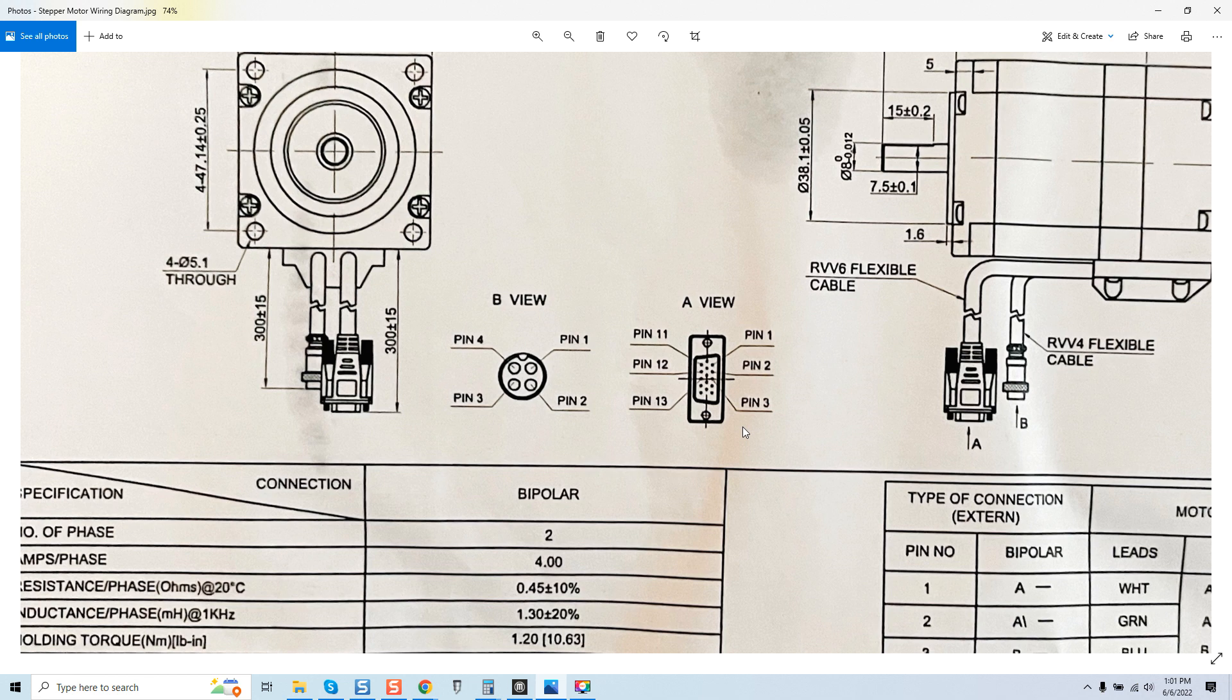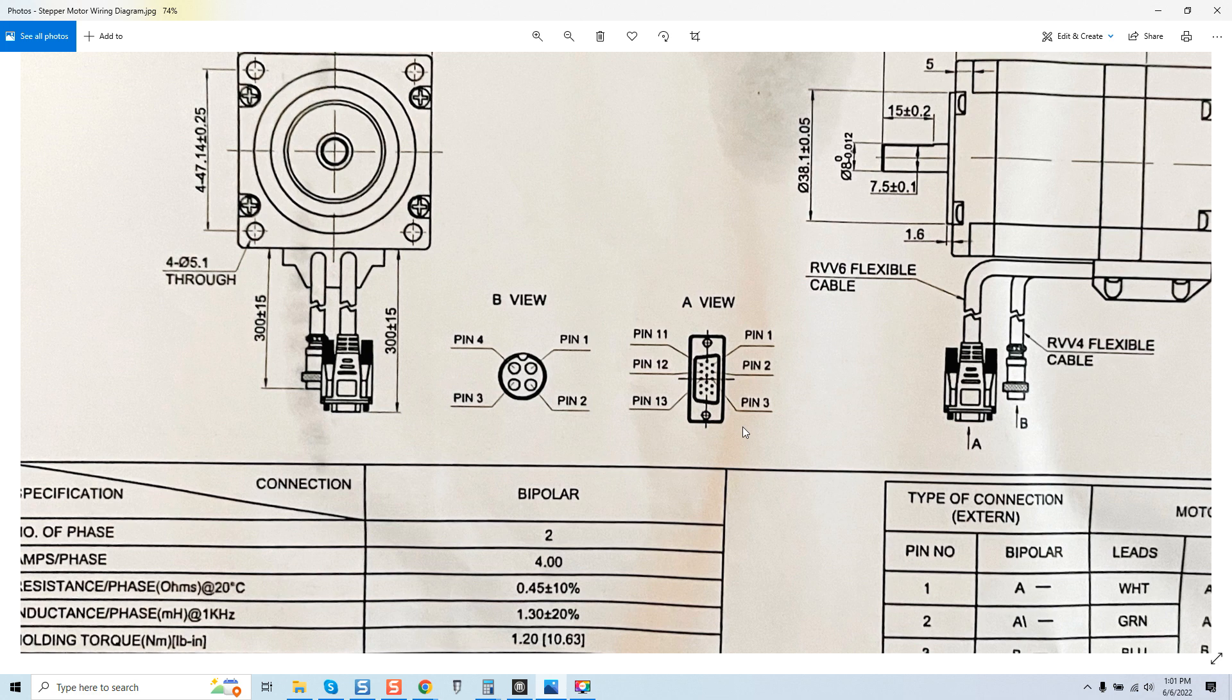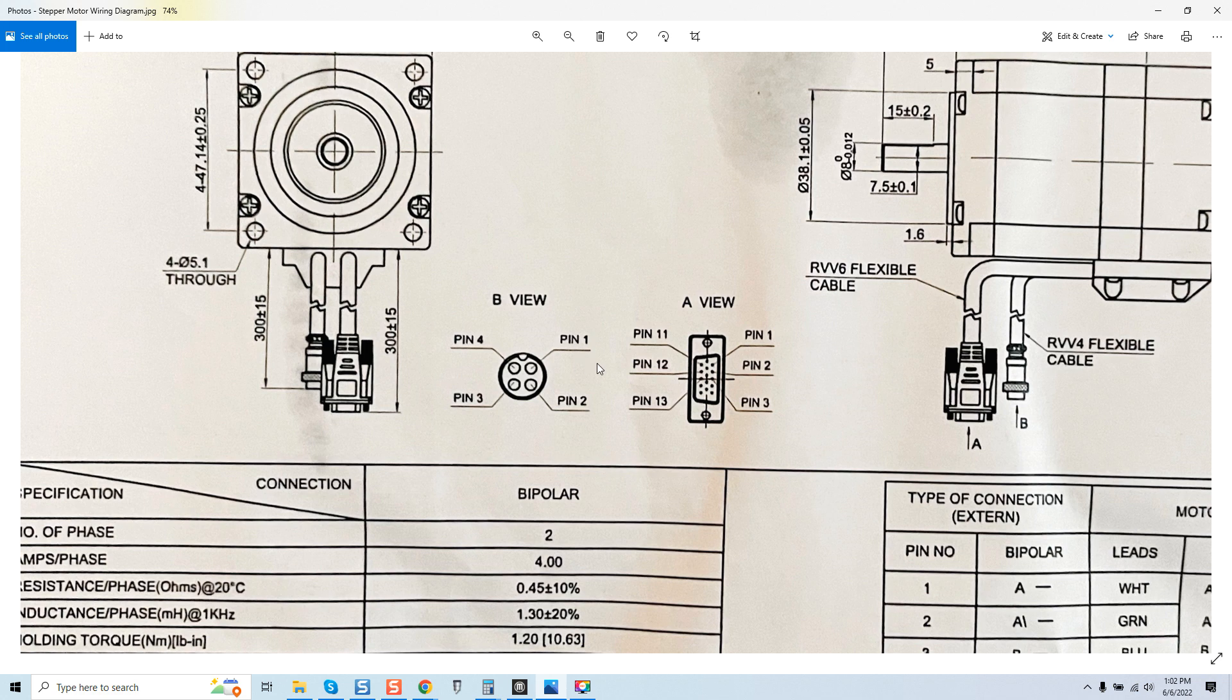I mean if you're really needing a cable that long you have to look at where you're going to locate your controller because if that signal strength is too weak having the encoder becomes essentially all but useless. So again we have to pay attention to voltage drop all the way across the board and you're always paying attention once again to what makes monetarily the most sense.